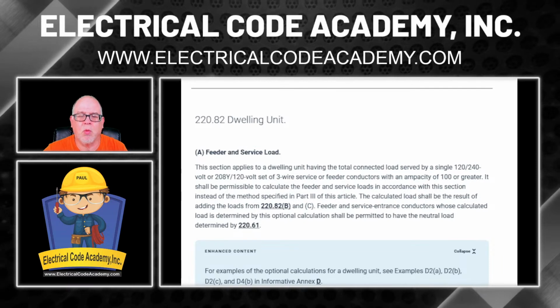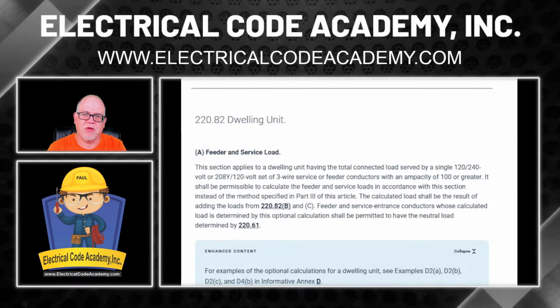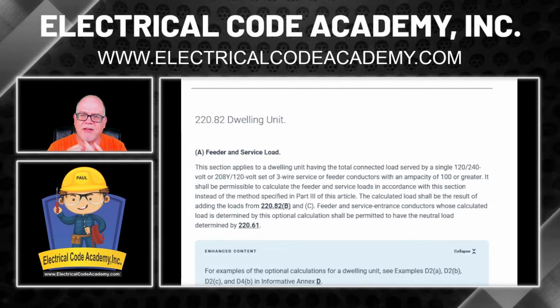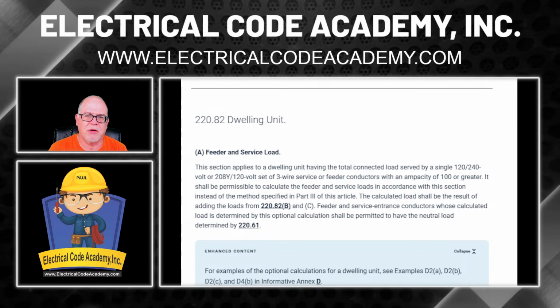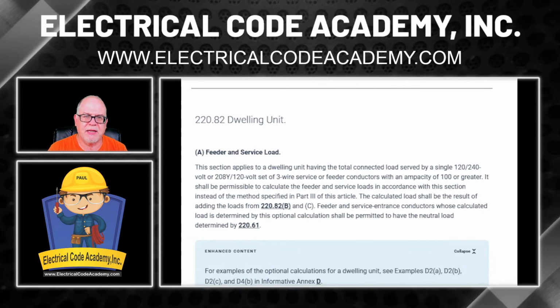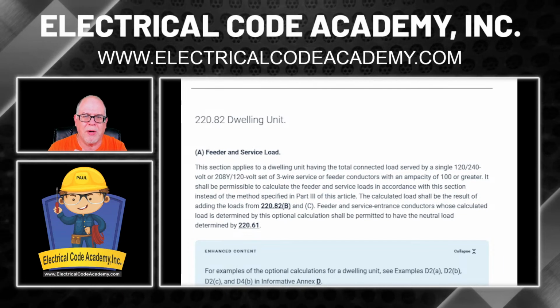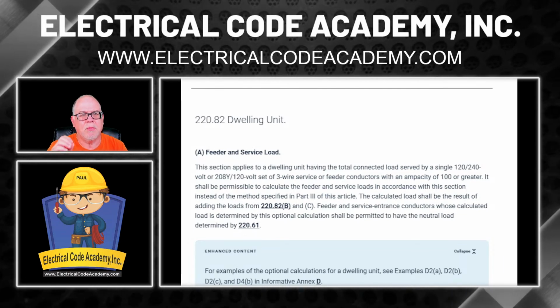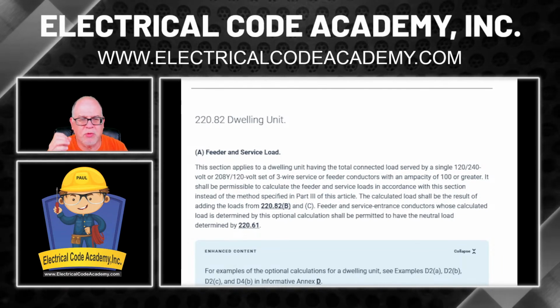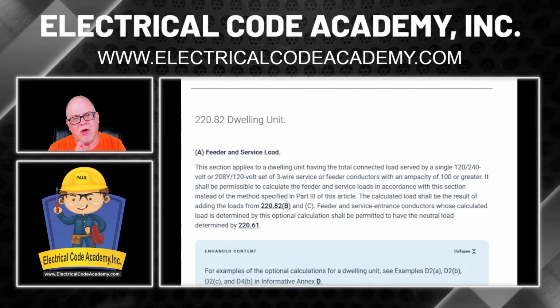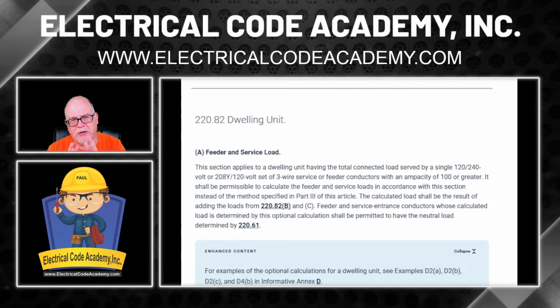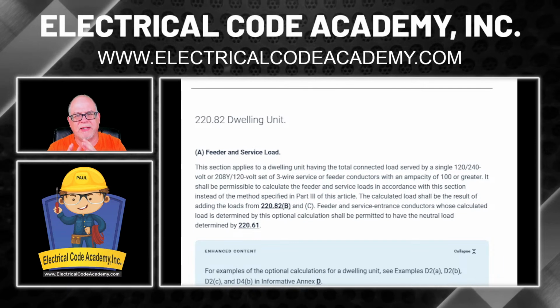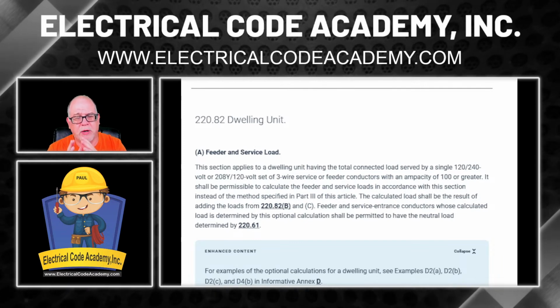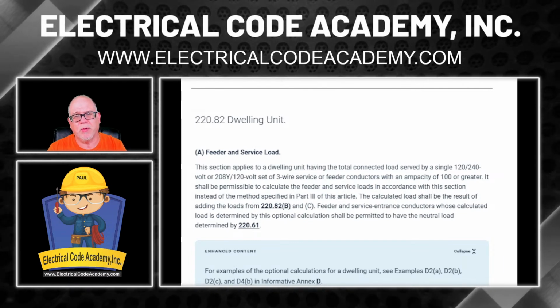All right. So what you see is it talks about feeder and service loads, and it tells us that since it's a dwelling unit, we're going to follow this optional method if it's a 120/240 or a 208Y120. Well, we know that even though it was 230 and 115, the nominals are 120/240. So we know that we're dealing with a single phase 120/240. But that's not the most important part here.